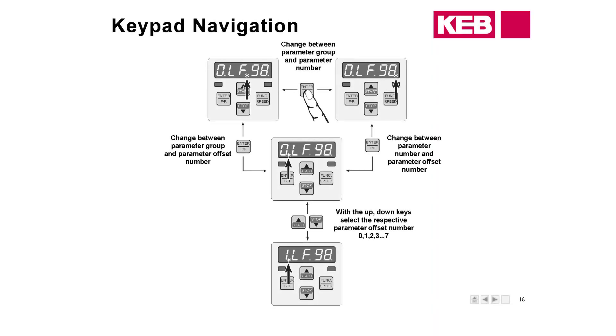In this example we're looking at the fault log. If you're wondering what faults you have or have seen, the most recent fault is going to be in parameter 0 LF 98 — that's the one that happened most recently. To view the next most recent fault, hit the Enter button; the flashing cursor will move to the left side of the screen, then arrow up to 1 and hit Function, and the corresponding fault will appear.